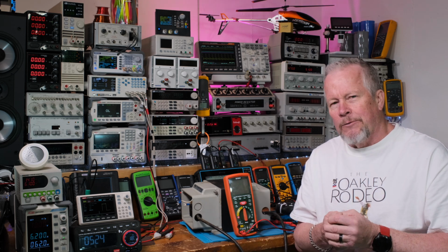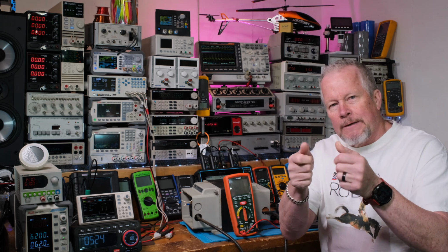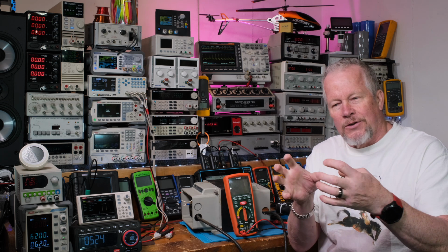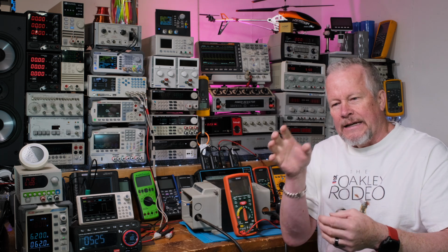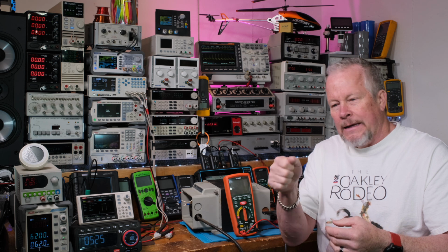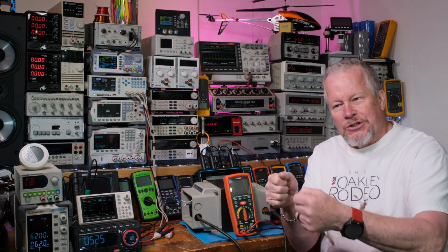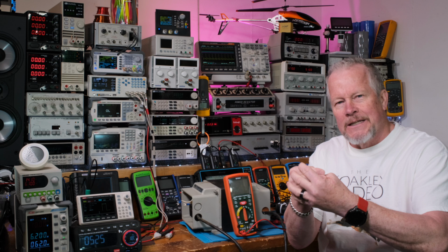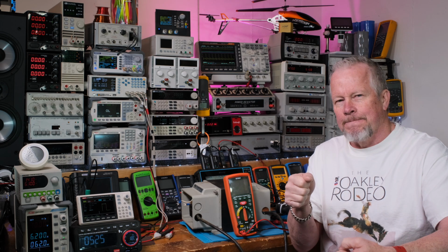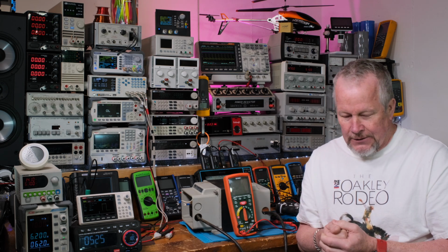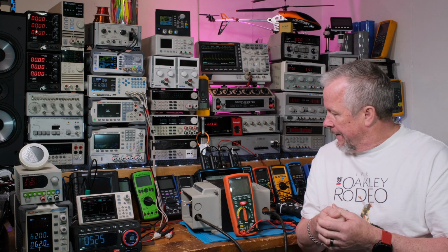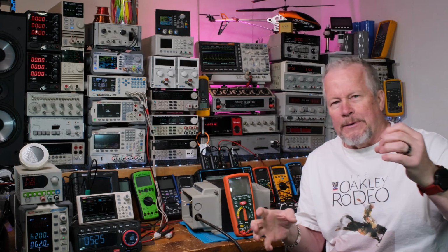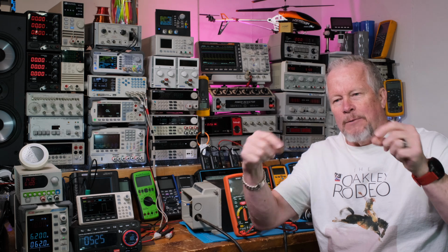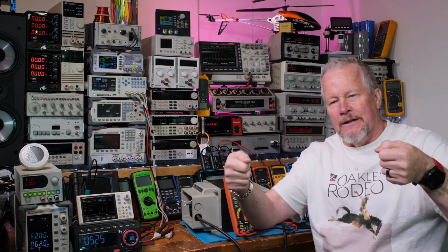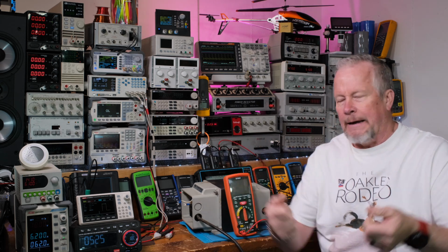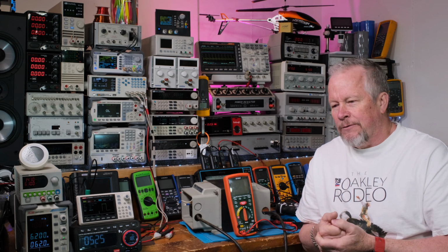By the way, normally when I do a test like this, I'd hook up all the windings together with jumpers so they're all shorted together, all the terminals, and take a wire from that to one side of my HiPot and then go to chassis. So I'm chassis testing all the wires connected in parallel to chassis and seeing if that breaks down. That's the normal way I'd do it. You take all the wires on the primary side, all the wires on the secondary side, short all the pins together, take a wire from each side, and test them all at one time. That's usually the quick way.